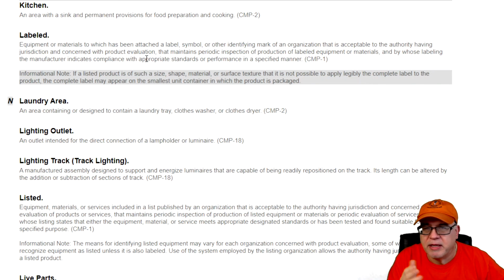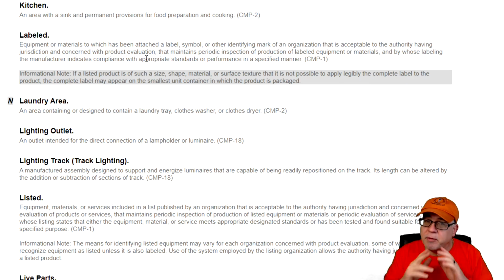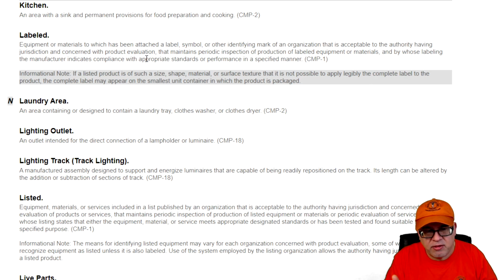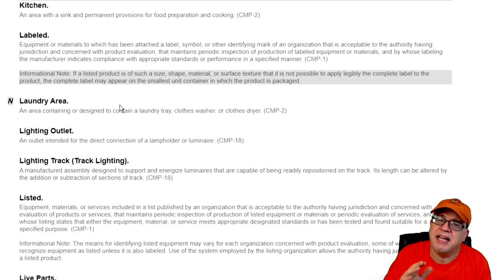Example, MC cable, UL 1569. That's an ANSI UL standard. When we apply the labels to the packaging, because you don't have to apply it to the cable itself. It's metal, for goodness sakes. But if you apply it to the labels on the packaging, then we are basically labeling, telling you that it has been evaluated. It was constructed, manufactured, and a third party, non-interested party, okay, has come in and evaluated that, yes, so-and-so made that product to the minimum standard that's required, okay? And that's what labeling is, and that's physically a label, okay?